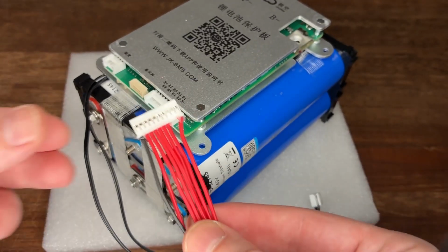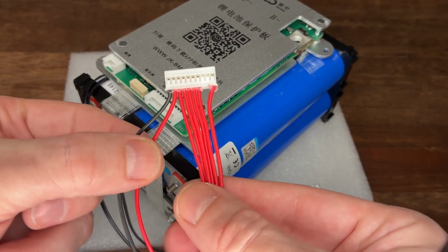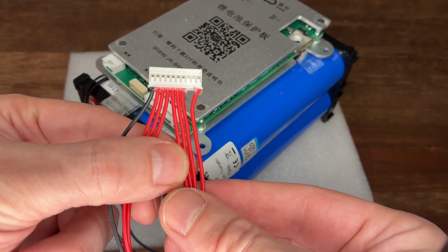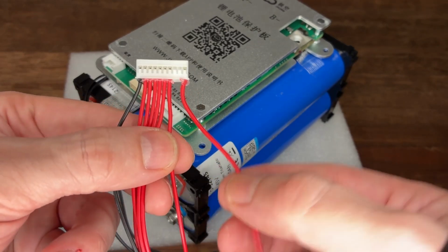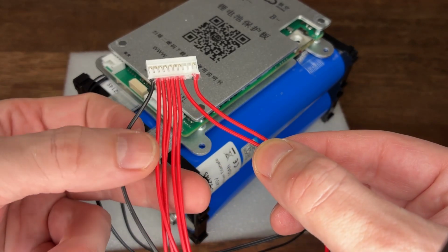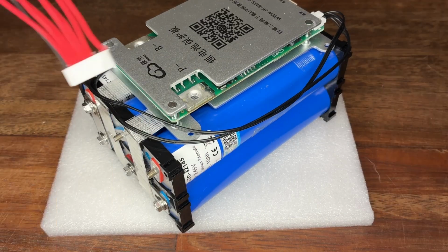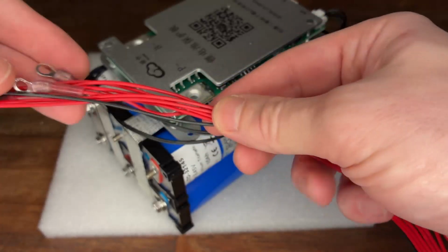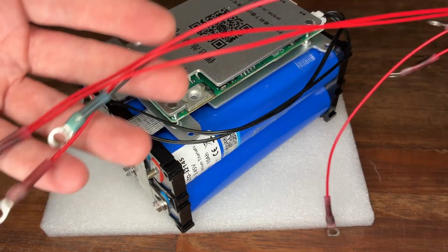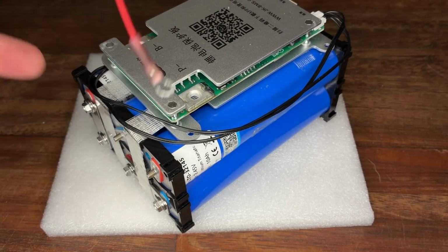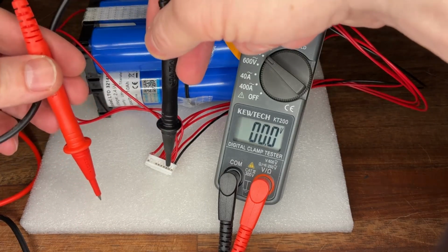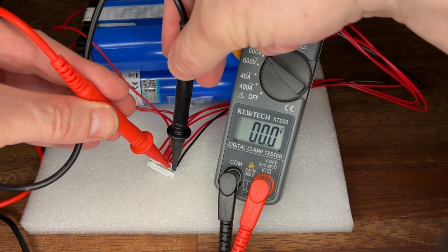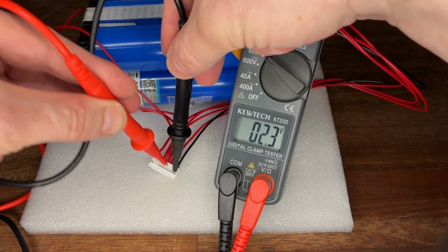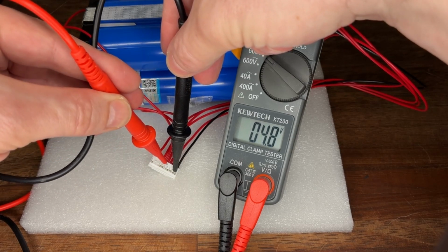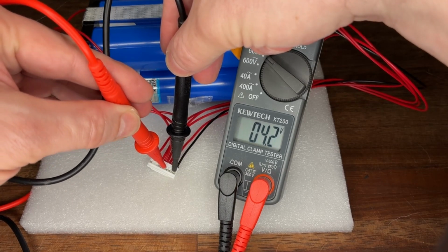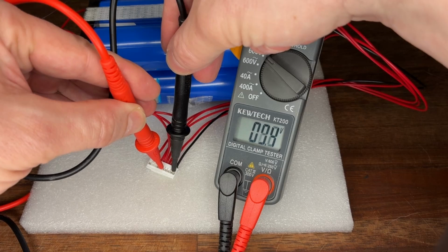Starting from the left, the main negative terminal of the battery, then the positive terminals for cells 1 through 6. The final wire also connects to the positive terminal of the 6th cell, which serves as the main positive terminal. It's also important to ensure the cables for each cell are the correct length. We'll finish the end of every wire with a proper ring terminal. Before connecting the BMS, we check the voltage in the connector to ensure it is connected to the battery in the correct order. As we move down the balance leads, you can see the cumulative voltage rising cell by cell.